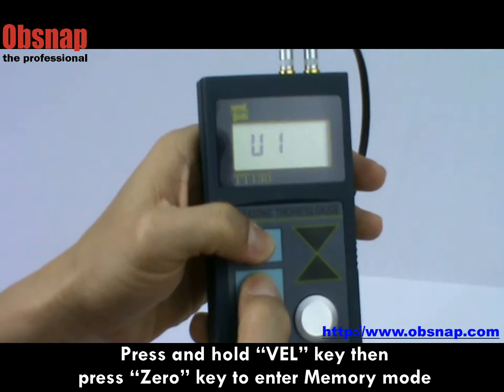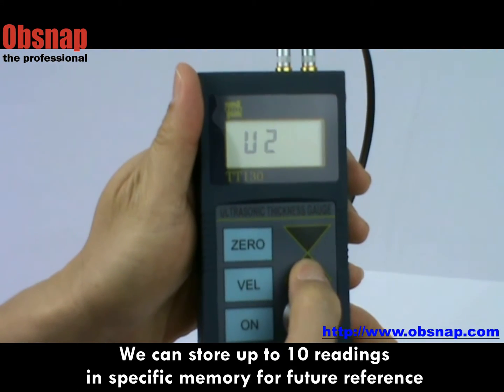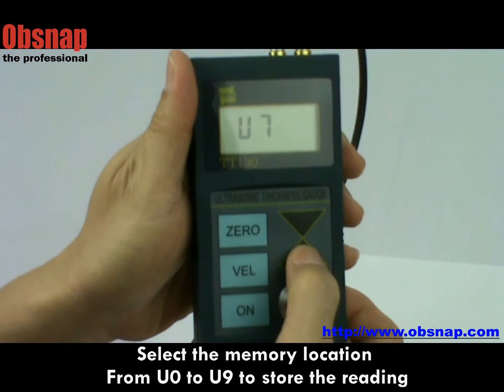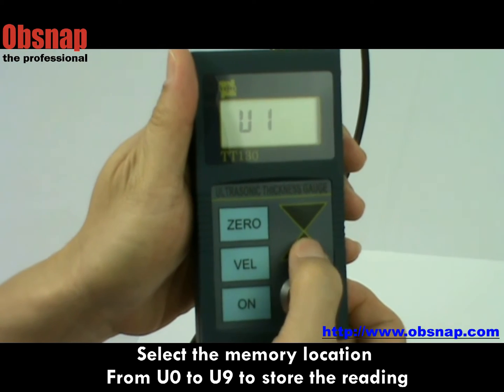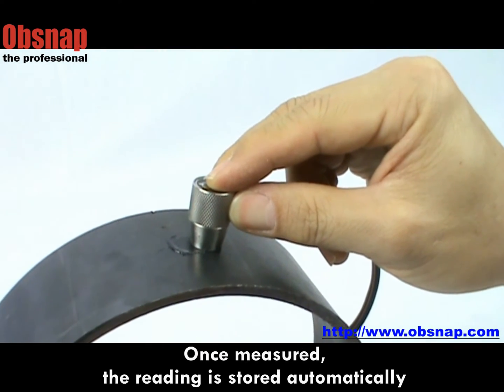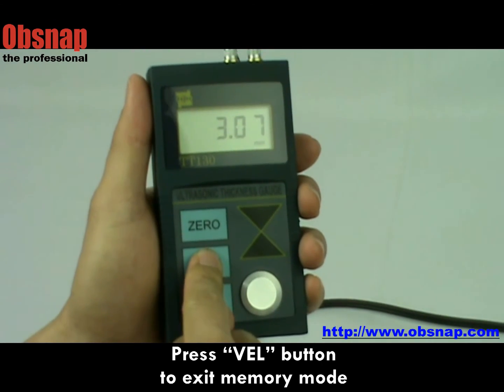We can store readings in memory. Press and hold the VEL key and zero key to enter memory mode. We can store up to 10 readings. Select the memory location from U0 to U9 to store the reading. Once measured, the reading is stored automatically. Press the VEL button to exit memory mode.